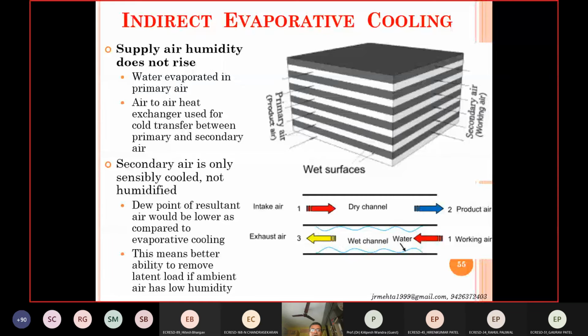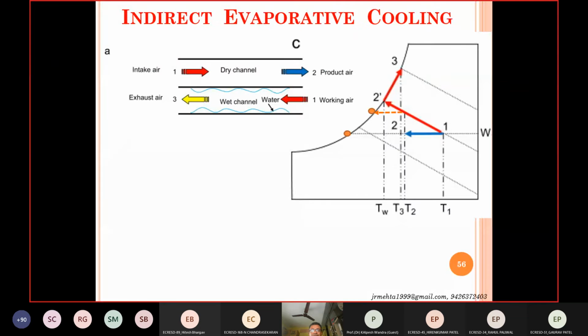Then the indirect evaporative cooling system. Why are we going for indirect evaporative cooling as compared to evaporative cooling? The reason is that here there is indirect heat exchange between the primary air, where the evaporation occurs, and the air which is going to be utilized for air conditioning purposes. Because of that, you are not humidifying the air that is being supplied into the space. You are just cooling it. But there is an additional heat exchanger here, so the initial cost would be higher as compared to evaporative cooling, and there will be more pressure drop, so your blower power will be higher. So this explains how evaporative cooling can help you to cool the air sensibly without adding moisture into it.